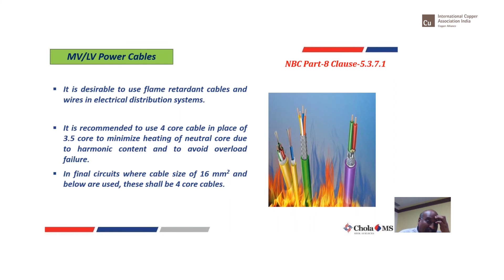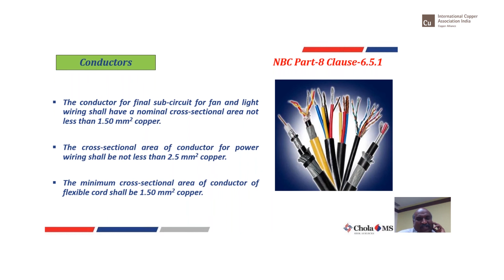And coming to the size of cables, please don't go anything less than 1.5 copper for your lighting or small fan or anything. Always ensure that, okay, for some communication electronics, say LAN, there could be some different sizing, but standards have clearly said not to use any cables which are less than 1.5 square mm. And for higher sizes, you properly calculate and use the right size.